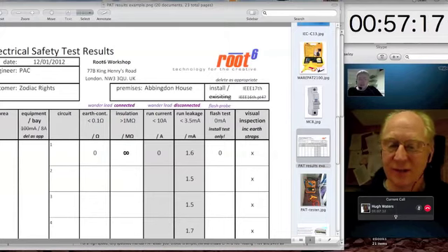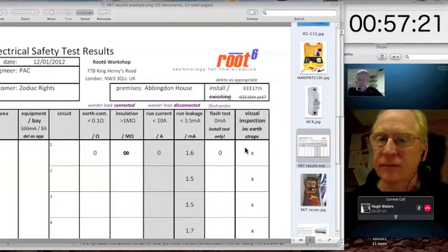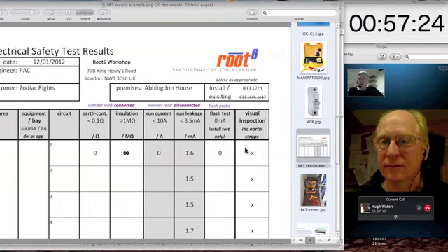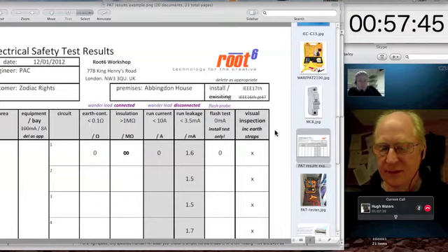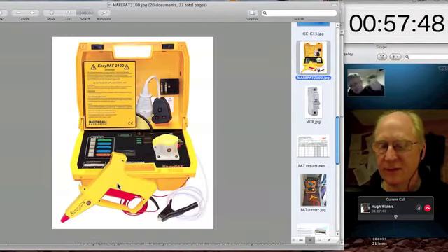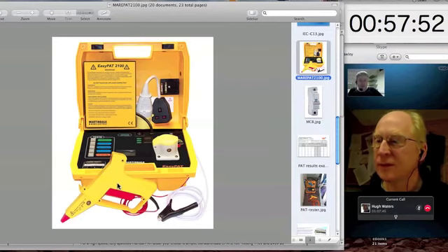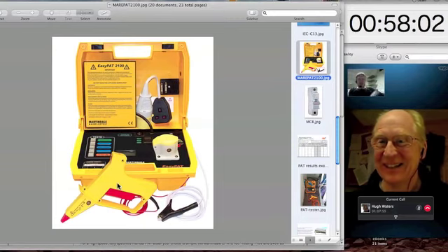But that's why, yes. Now, the last test that the machine does is called the flash test, and it's an optional test. It's typically only recommended for where you're going to be powering Class 1 equipment. What it does is it applies 1,500 volts of AC between the phase and the neutral, the live and the neutral joined together, and Earth. So in that way, it's very similar to the insulation test. But it does it using this probe, this flash probe, this thing here. And so you would typically put the flash probe onto some exposed metalwork on the cabinet, and then you press the flash button on the PAT tester, having first told all your colleagues to take their hands off the bays, because 1.5 kilovolts, although it doesn't have very much current carrying capacity, is a nasty nip.